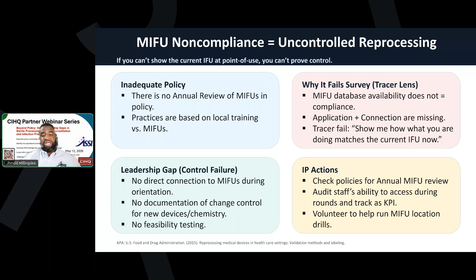The next leadership gap opportunity is that sometimes we treat washers like magical cleaning devices. So we get mad when the surgeons ask us to sterilize wrenches from Home Depot or things that they invented, spoons that they hammered and cut in their garage. But we kind of do the same thing with washers, right? The policy doesn't talk about rejection criteria for running items on the wrong cycle. There's a cycle for ophthalmic instruments that don't get lubrication and should not get enzymatic. Orthopedic cycles have longer thermal rinses, longer soak periods, and sometimes we're called into the bioburden. At the end of the first day, we audited 31 washer cycles, every single one with orthopedic instruments on them. Every single one of them was run on the plain instrument cycle.